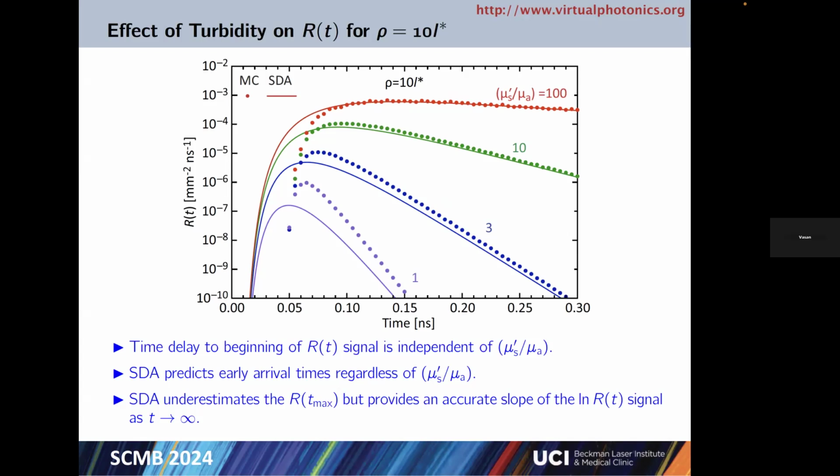That's actually really important, both in time domain and frequency domain, is the impact of, no system is ideal. You never have this perfect delta function in terms of your source, or perfect sine wave in terms of your intensity modulated source. And then on your detection end, photomultiplier tubes are great, but it's not like they have instantaneous response with no temporal dispersion. And if you have temporal dispersion in your response, that's really going to compromise your ability to recover mu a and mu s prime, because you actually never detect these signals.